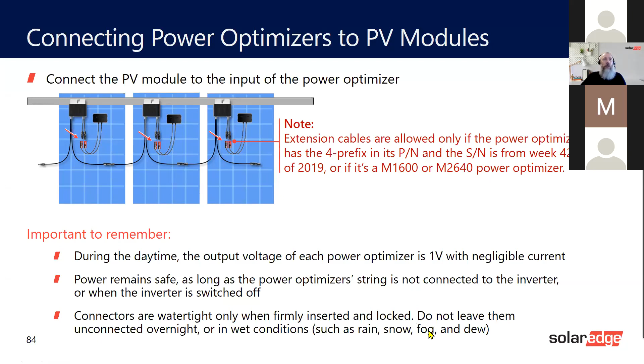Not on the M1600 though. It says here connectors are watertight only when firmly inserted and locked. Do not leave them unconnected overnight or in wet conditions. Once dampness gets into the optimizer and then you plug it into the module or to each other, it's not going to go anywhere - it will stay there and cause a problem with communication.